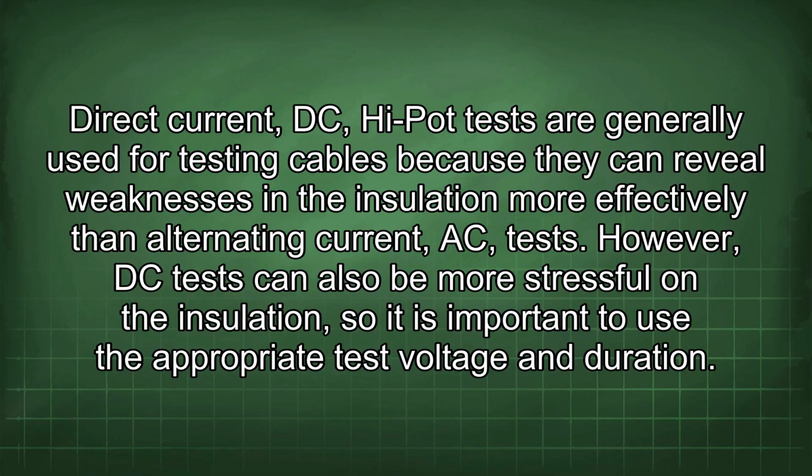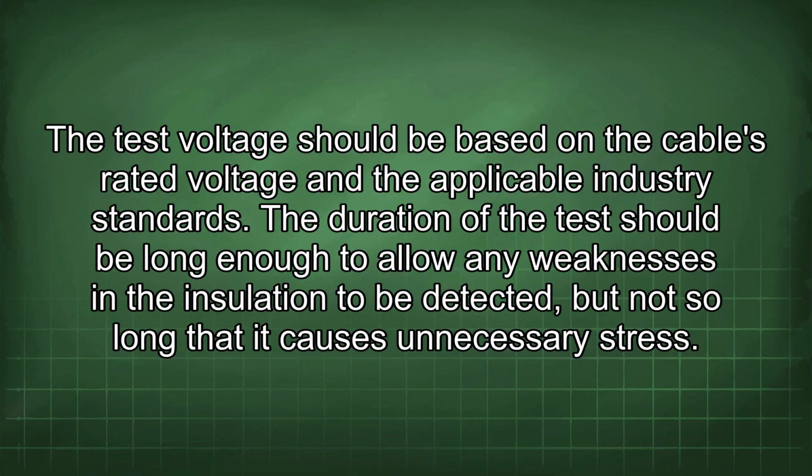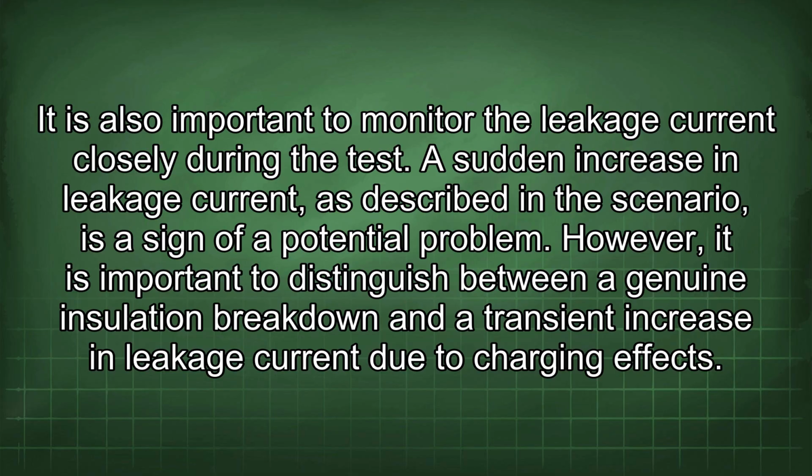However, DC tests can also be more stressful on the insulation, so it is important to use the appropriate test voltage and duration. The test voltage should be based on the cable's rated voltage and the applicable industry standards. The duration of the test should be long enough to allow any weaknesses in the insulation to be detected, but not so long that it causes unnecessary stress. It is also important to monitor the leakage current closely during the test.